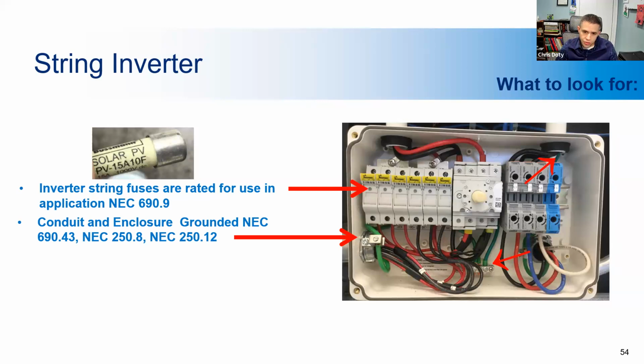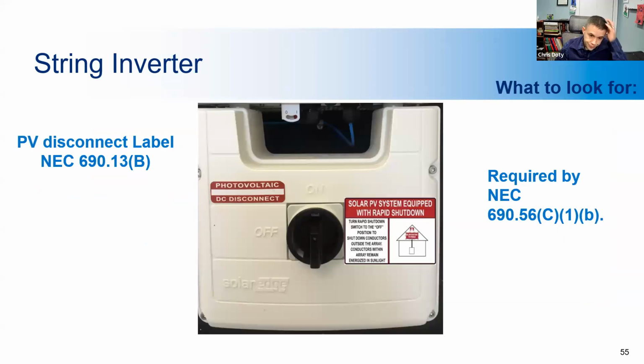And you also want to check conductor sizing again, by looking at the markings on the wire, as well as the fusing requirements. Fuses have to be rated for solar PV, not just for any DC use. For residential, that's 600 volts DC solar, and for commercial, it's 1,000 volts DC solar. So you want to keep that in mind. Make sure that the fuses are actually rated for solar.